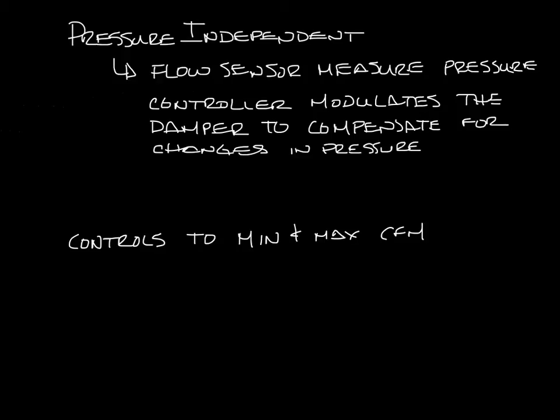So at any given CFM, let's call it CFM 1, if the pressure in the system goes up, the damper is going to close down to maintain CFM 1. That's how pressure independent VAV boxes work.